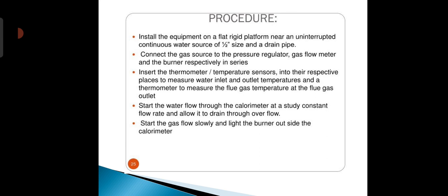Next, the procedure. Install the equipment on a flat rigid platform near an unobstructed continuous water source of 1/2 inch size and drain pipe. Connect the gas source to the pressure regulator, the gas flow meter, and the burner respectively in series.